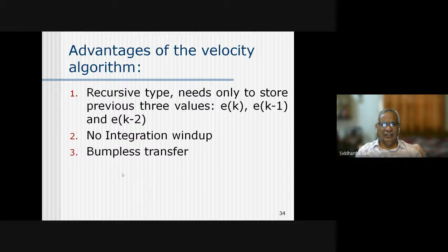What is integration wind-up? If there is a certain large change in set point, the error will be large because the set point has changed, but the output is small, I mean it has not changed. The integrator output in a PI controller will build up and increase with time, because if we integrate any error it will build up. As a result, the controller output may exceed the saturation limit of the actuator. This wind up, unless prevented, will cause continuous oscillation in the process. This is a big problem in the practical implementation, and it has to be taken care of, which can be handled by this velocity algorithm.